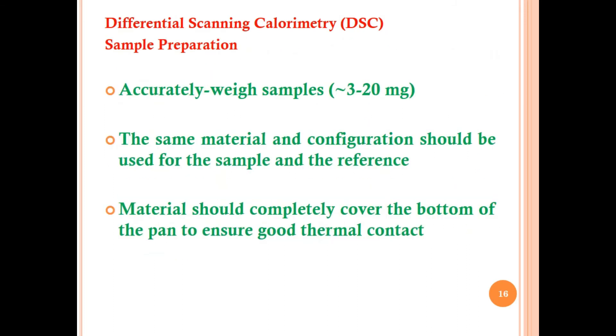In sample preparation for differential scanning calorimetry, the sample is accurately weighed at about 3 to 20 mg. The same material and pan configuration should be used for both sample and reference. The material should completely cover the bottom of the pan to ensure good thermal contact, meaning it fully acquires the programmed temperature.